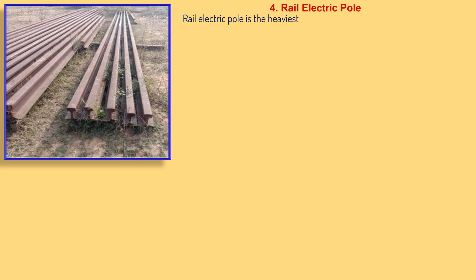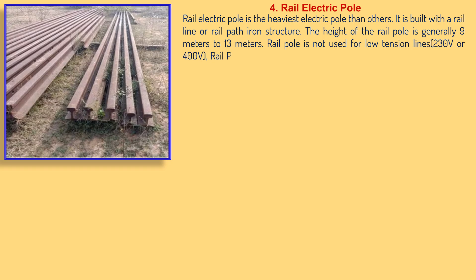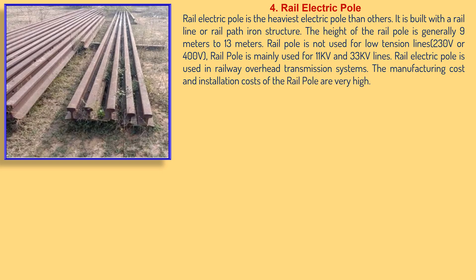The rail electric pole is the heaviest electric pole. It is built with a rail line or rail path iron structure. The height of the rail pole is generally 9 to 13 metres. A rail pole is not used for low-tension lines like 230V or 400V; it is mainly used for 11kV and 33kV lines. It is also used in railway overhead transmission line systems. The manufacturing and installation cost of the rail pole are very high. These poles are used in cities, urban areas, near highway crossings, and for 11kV, 33kV, and 66kV.